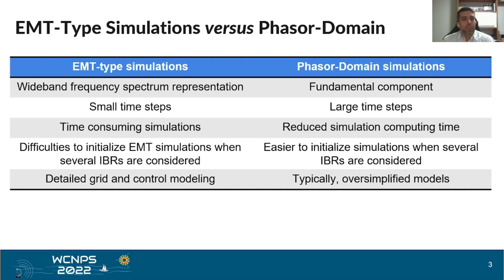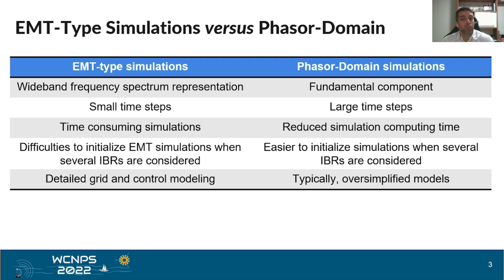This table compares EMT-type simulations and phasor domain simulations. Starting with EMT-type simulations, they are capable of representing wideband frequency spectrums and simulating higher frequencies; small time steps are required, which result in time-consuming simulations. There are also some difficulties to initialize EMT simulations when several IBRs are considered in the same simulation case. But even with these drawbacks, detailed grid and control modeling is possible.